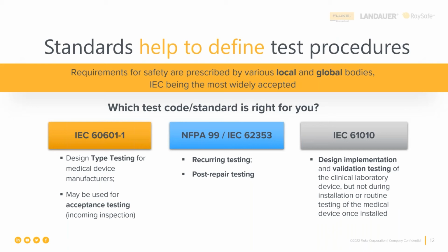IEC 61010, I want to just cover here, is specifically for clinical laboratory equipment. And it is for the manufacturer and their installer to perform. There's 2 tests that are required under this standard. Those need to be done by the manufacturer or the installer before they turn that part of the laboratory over for go live, for readiness for use by the hospital. So after that installation and that go live of the clinical laboratory equipment, then we will use the IEC 62353 ever after, until we install some new clinical laboratory equipment and get the handoff. That's what we'll do.